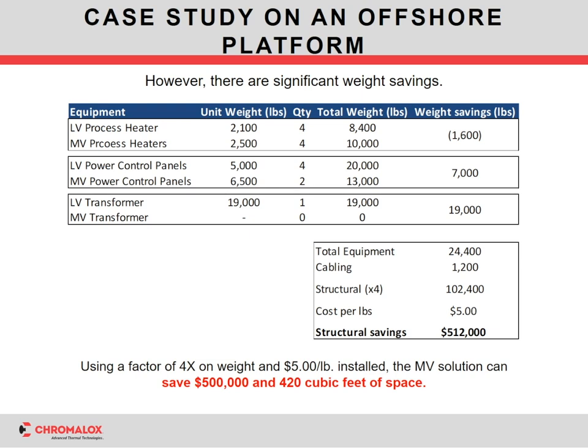And on an offshore floating platform, it's not only the weight of the equipment, but the structural support that it needs to go in there. So for every pound of equipment, they need approximately 4 pounds of steel or supporting structure to support that equipment. So when you look at the cost savings from a structural standpoint, the installation was actually able to save over $500,000 US for the customer, as well as minimizing the amount of space occupied for the equipment, since the transformer wasn't needed.